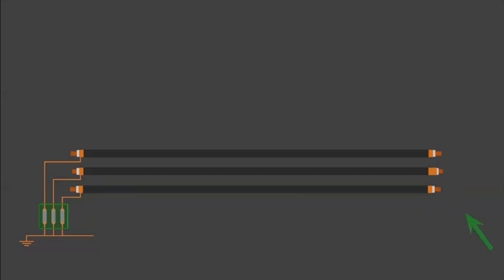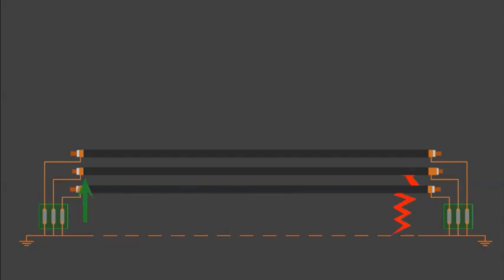If we also earth the sheath at another end, then there will be a circulating path created through the sheath and the earth. Due to this circulating path, there will be an induced circulating current flowing through the sheath continuously, which creates unnecessary heat loss in the sheath, and this can make derating of the cable. In the fault condition, this circulating current will be huge. So in general, to avoid the circulating current, we avoid earthing of the sheath at two ends.